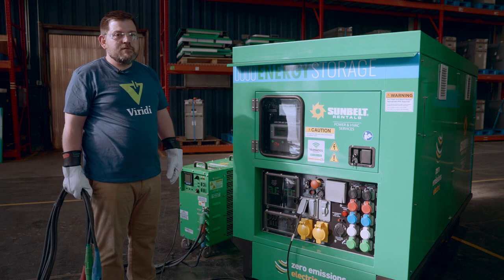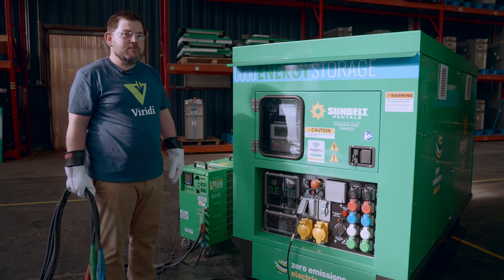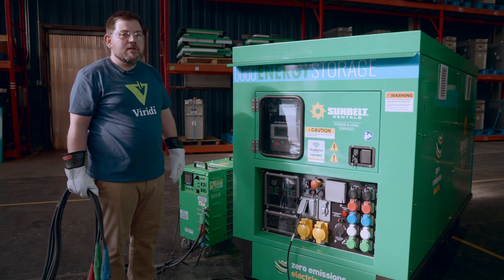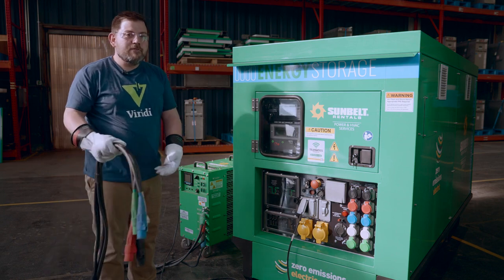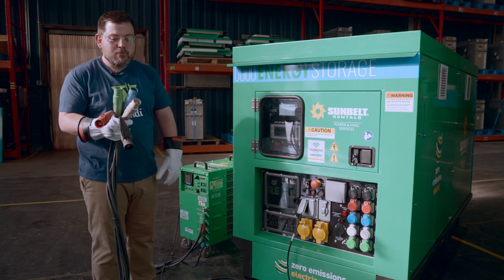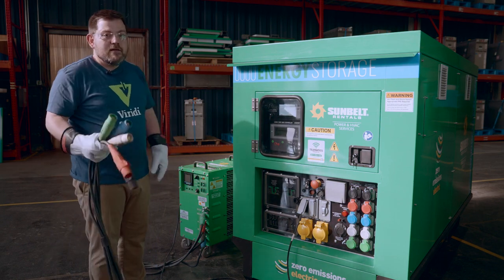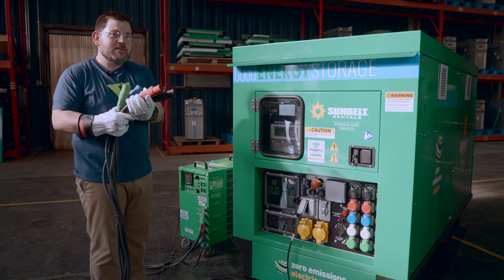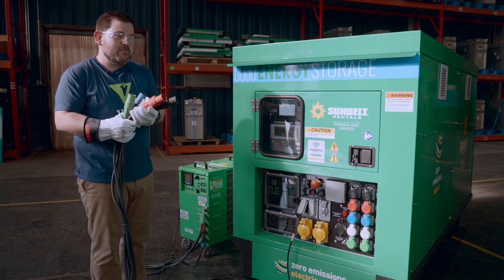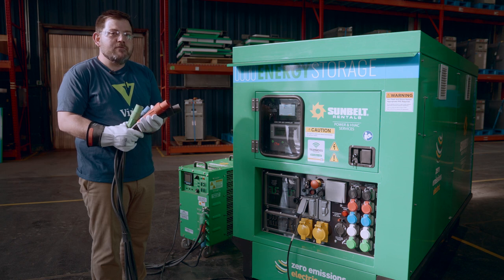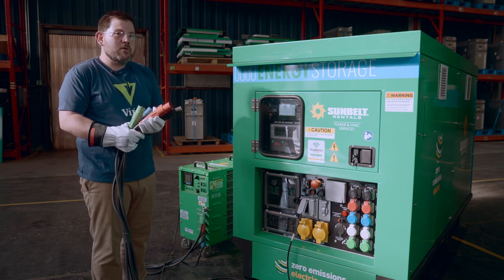Now I'm going to go through some of the mode selection and mode setups for the SBR30-150. First mode I'm going to do is our off-grid discharge example with an actual Sunbelt load bank. I'm going to hook up our cam locks to the load grid side cam lock setup, put our transfer switch in the 480 volt position, and select the mode on the user interface.